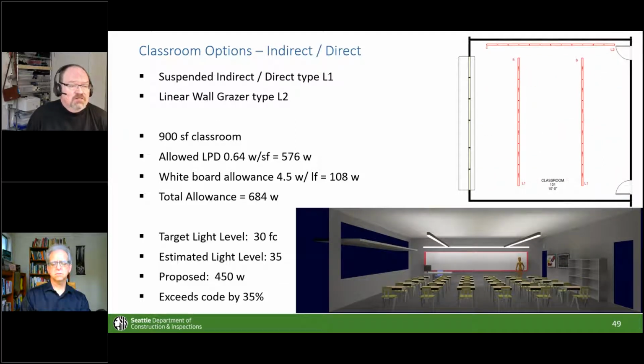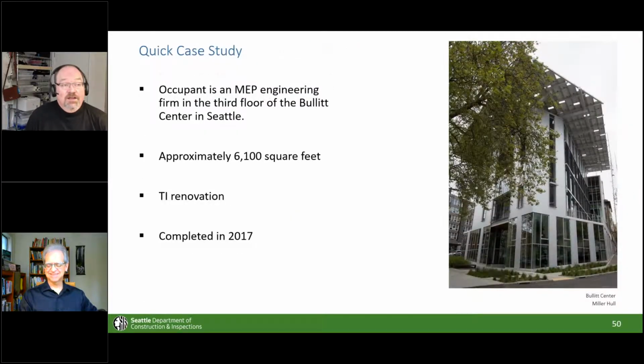Same classroom, but in this particular case, it's indirect direct lighting because we've bumped our ceiling up to 10 feet, right? So we've got that height to provide us what is, frankly, from my perspective, better lighting. If we can get that higher ceiling, we get better daylight within the space. And then we also get the ability to have indirect direct lighting, which is personal preference. Similarly, the allowance remains 684 watts, our proposed is a little bit higher because we're doing indirect direct lighting, but we're only exceeding the code by 35%. Shocking, but essentially the same kind of light level.